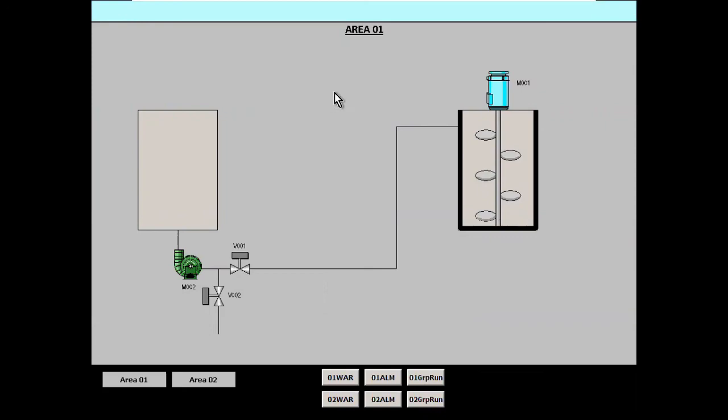Like we said, what are the preconditions? What can happen if this agitator is started when the tank is full or half full? What will happen to the starter current of that motor? Do we need to make that motor have a star delta starter, or does it need to have a soft starter? And then how do you allow for the run feedback in that instance to be delayed by 30 seconds to maybe 60 seconds? Again, sorry, I digress.